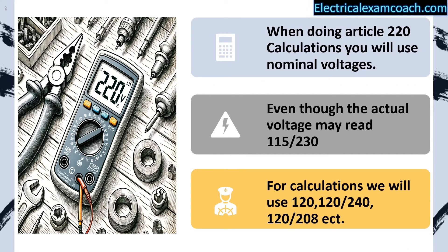When doing article 220 load calculations, we're gonna be using nominal voltages. Although our actual meter reading might be 115 or 230, for our calculations we're gonna be using nominal system voltages like 120, 240, 120/208. It makes it a lot easier to do these calculations, not having to guess or wonder what the actual voltage readings might be.